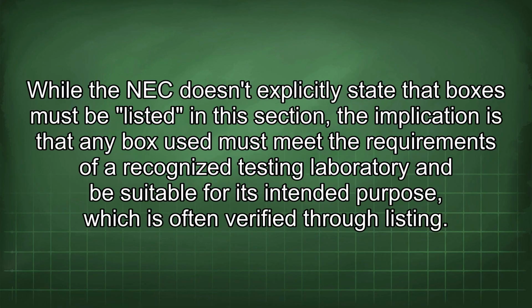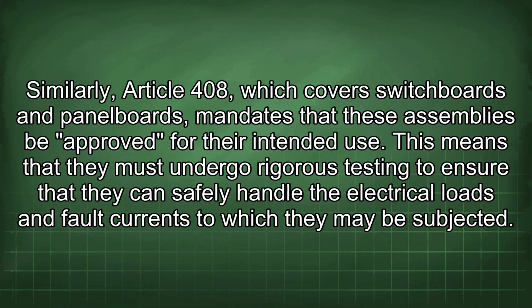While the NEC doesn't explicitly state that boxes must be listed in this section, the implication is that any box used must meet the requirements of a recognized testing laboratory and be suitable for its intended purpose, which is often verified through listing. Similarly, Article 408, which covers switchboards and panelboards, mandates that these assemblies be approved for their intended use. This means that they must undergo rigorous testing to ensure that they can safely handle the electrical loads and fault currents to which they may be subjected.